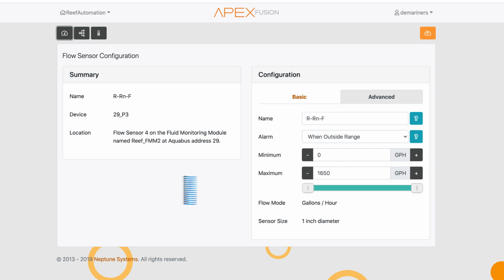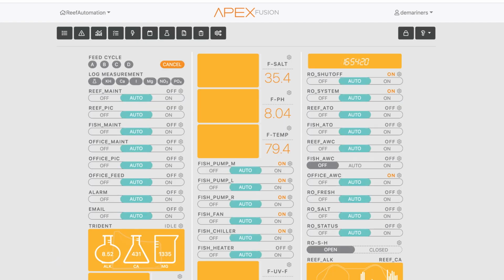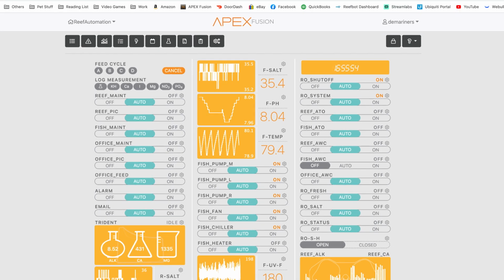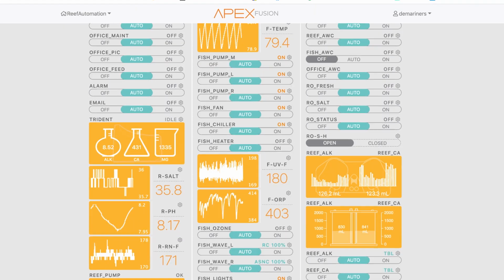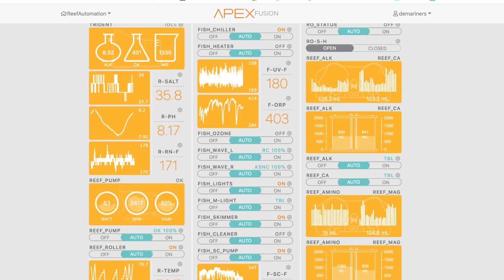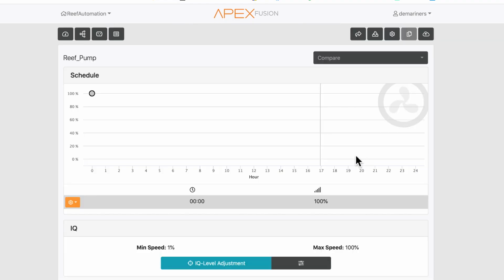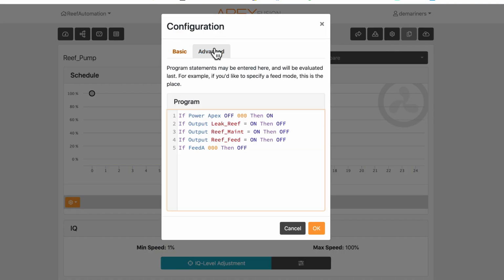Now you can use your flow sensor for a number of reasons. So let's say you wanted to control a pump with a flow, or you wanted to see something turn off and on depending on the flow. This is how you would do that. So our flow is R return F, for instance. So let's say on my Reef pump, I want to program if my flow gets a certain value on my Reef pump, I want to turn it off or I want to turn it on. So what you can do here is you could say if our return is, let's say, less than 40, then off. Now what that would mean is that my return pump has indicated that it has a flow that's less than 40. I want you to shut off my return pump.